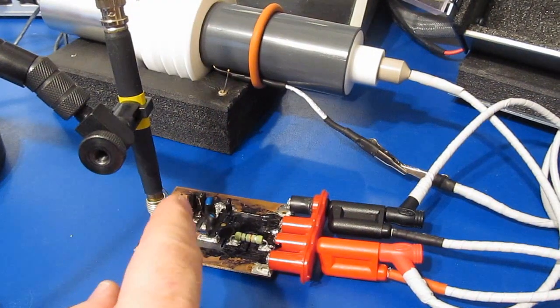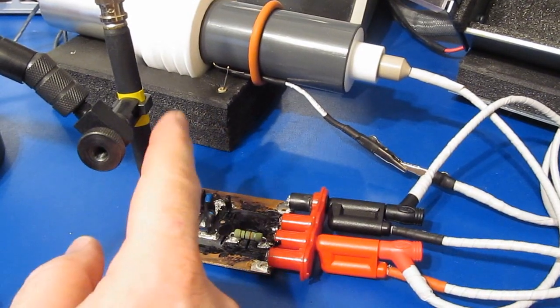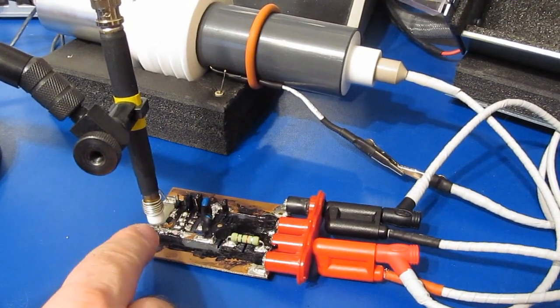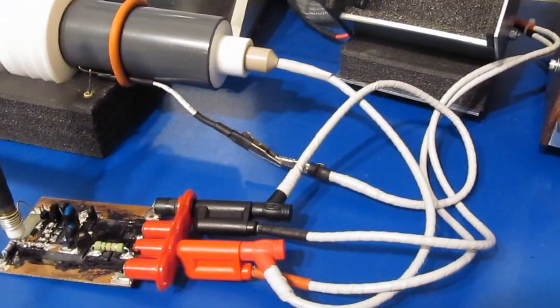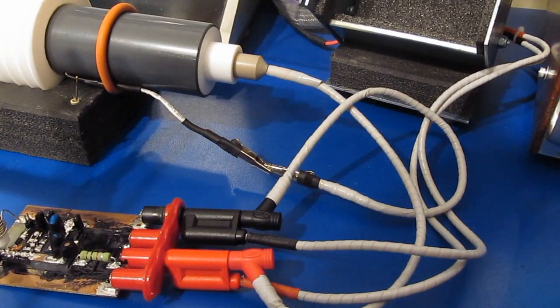I've changed our setup just a little bit. I now have this secondary high voltage probe attached to the output of the clamp. The transient generator is still set for 1000 volts. What I'm going to do is apply a couple more transients.